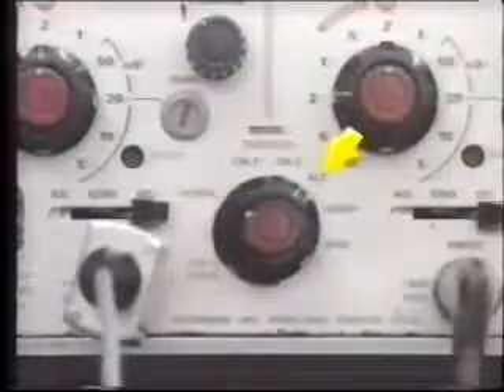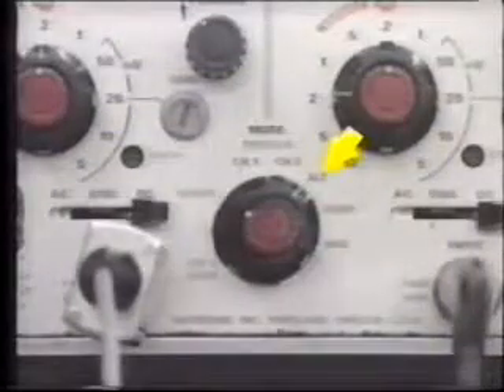The ALT mode is selected when measuring very high frequency signals. This causes the traces on channels 1 and 2 to alternate. At high frequencies, this is not noticeable, but it can cause an irritating flicker at lower frequencies, thus the CHOP selection.